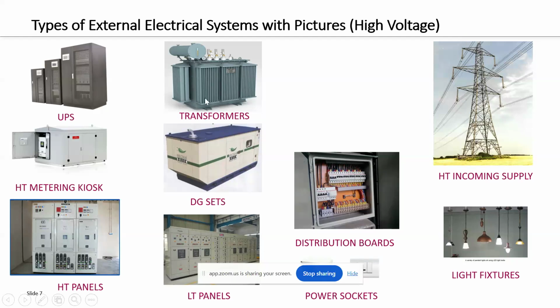Now what will happen from the transformer? The output goes into LT panels. Then there is further distribution. Along with the distribution, there is a DG set also for providing standby supply to the building. Now this will get connected with this LT panel system somewhere. How it will be done is a different thing. We are not going into those details. There are AMF panels to do that job. The DG set runs when there is no electricity supply from SEB.